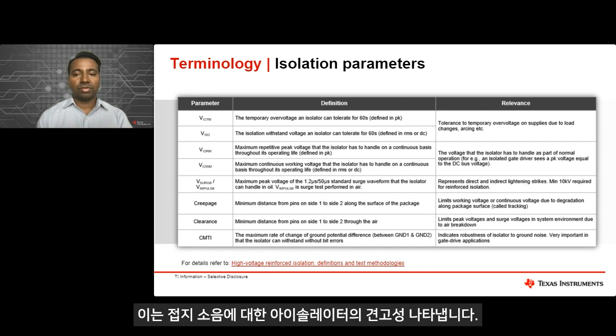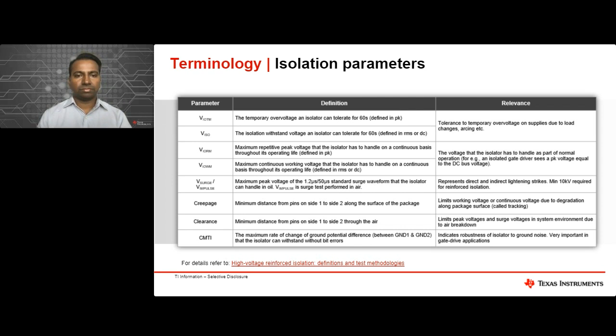CMTI, common mode transient immunity, is the maximum rate of change of ground potential difference between ground 1 and ground 2 that an isolator can withstand without bit errors. This indicates the robustness of the isolator to ground noise. And this is very important in gate drive applications like motor drive, traction inverter, solar inverter, and others.